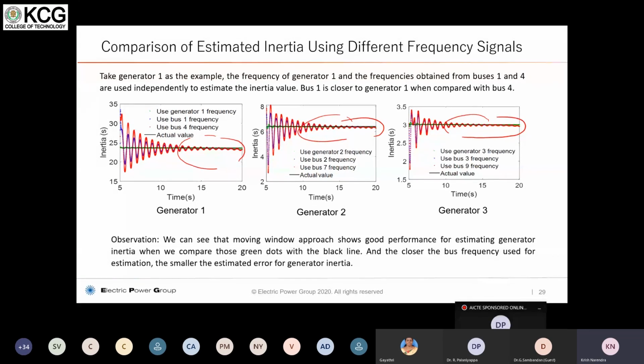Now, when a disturbance happens, the frequency moves like a transmission, traveling wave. It moves from one region to another until the disturbance goes off. Once the disturbance goes off, the frequency will again be constant and remain within a specified limit in the entire synchronous grid. So this shows that the evaluation of H at different locations is also very accurate.